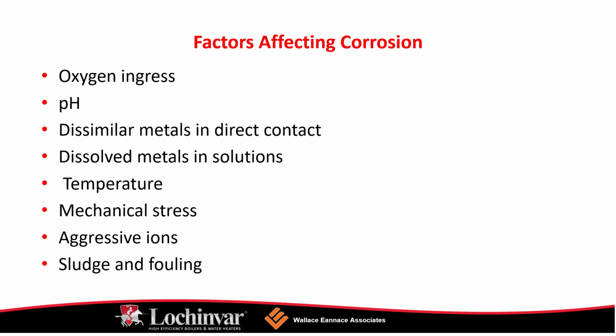Low flow areas, you'll have dead legs. What does this mean? Well, not your father's boiler. It's not an old school cast iron, low efficiency boiler. Our narrow waterways on these high efficiency boilers are subject to clogging. Again, relating to poor water quality.